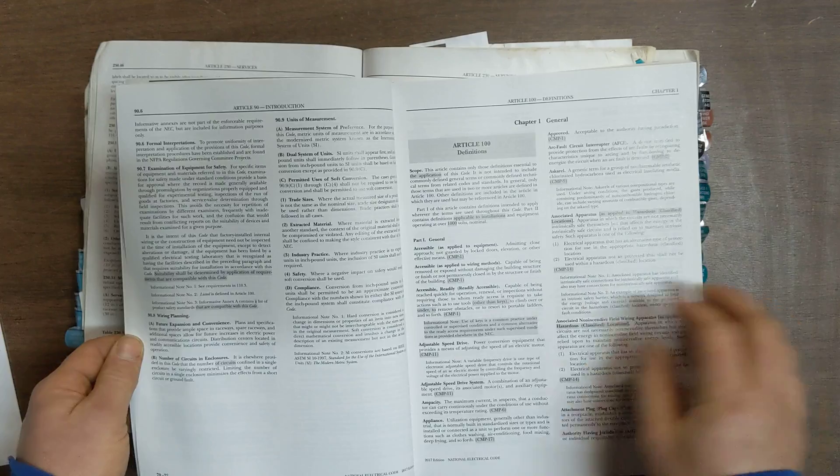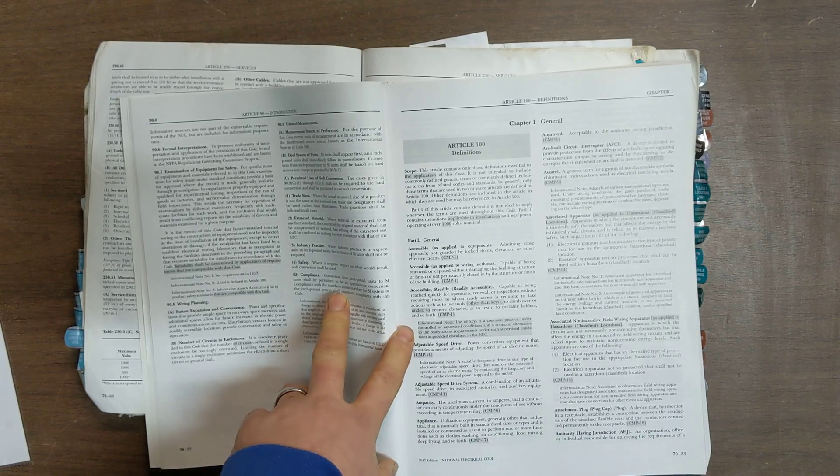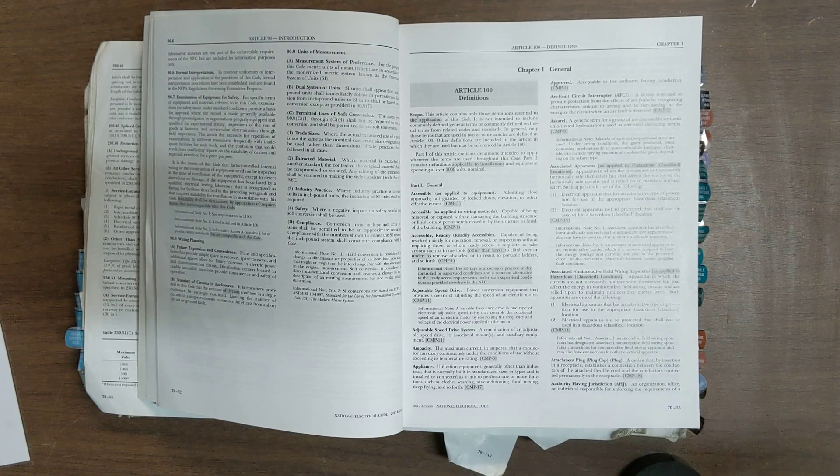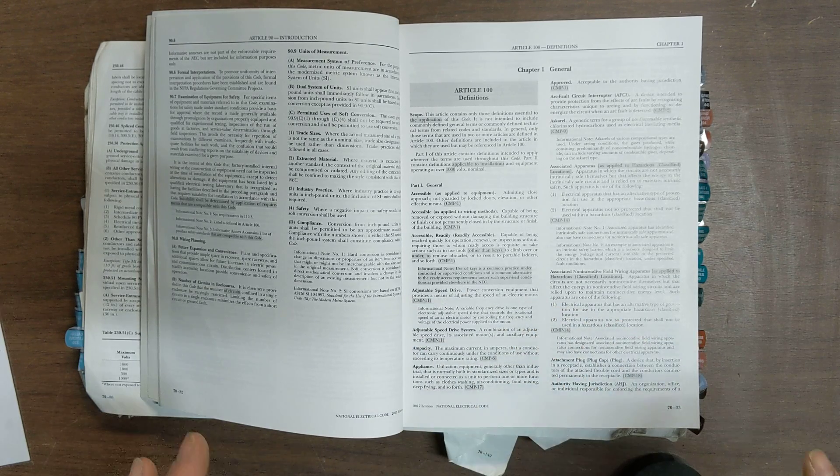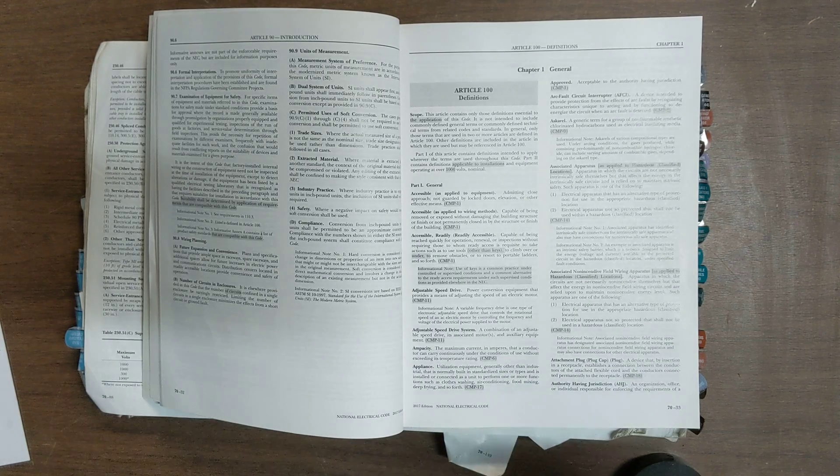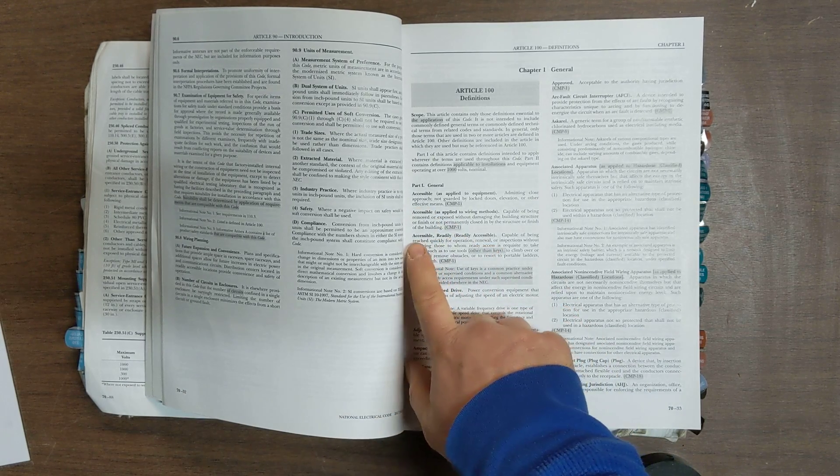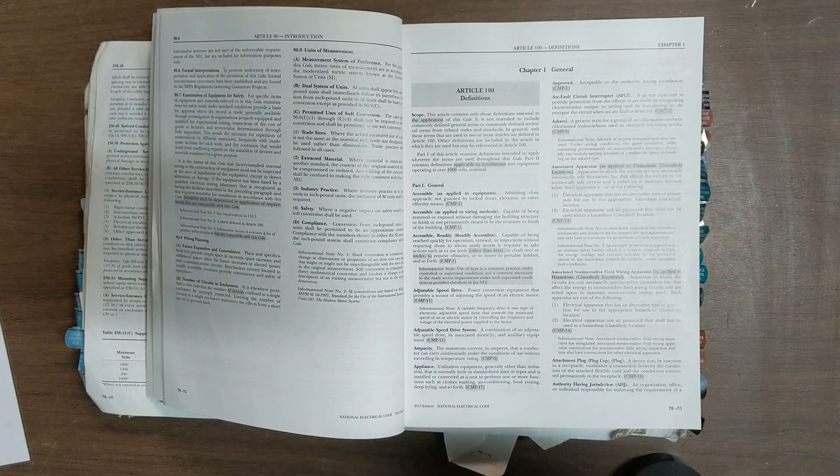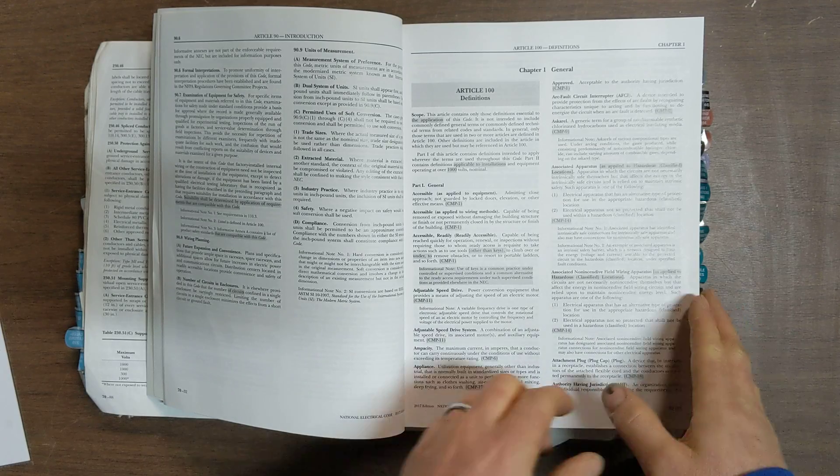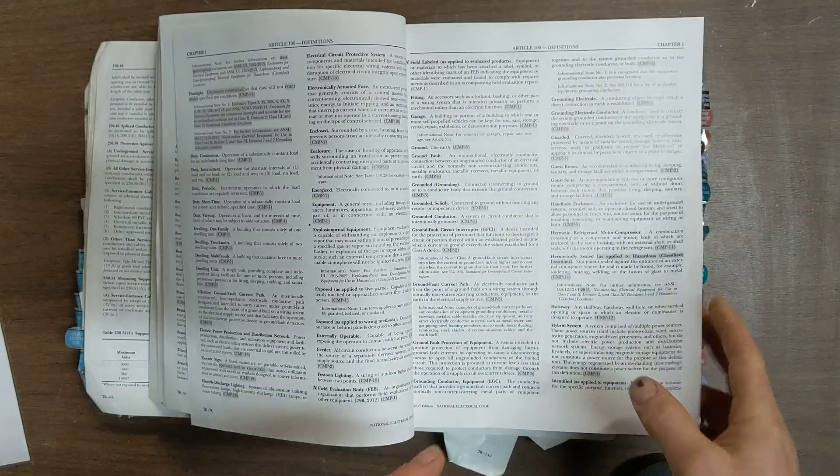So as we move forward here, if you look in article 100, you're going to find your definitions. You have to be very careful with definitions because sometimes the codebook does not put them in what I would think would be a practical manner. So a good example is we have accessible and readily accessible. You would think readily accessible may be in R's. So you're flipping over here in R's. It's just not there. But if you look here, it's listed like this. So you have accessible readily. So anytime you're doing a two-part definition, try going to either one of the words if you cannot find it in the section that you're in. You want to be very familiar with your definitions and what they mean. It can help you in the field and in your testing.